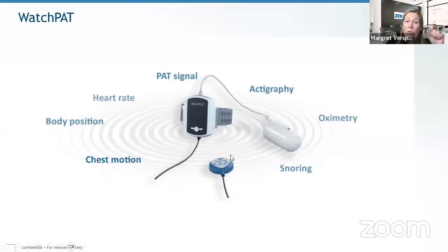Then there is also a microphone in the sensor. The microphone measures decibels of sound. It measures as if from 1 meter from the patient. So we can really see if the patient is snoring a lot, but also when the patient is moving a lot, we can get it from this sensor. So you need to be aware, and you can see in the raw data what's really going on. But also in the report, you can already get an idea if it's really snoring, yes or no, or related to movements. So that's the sound.